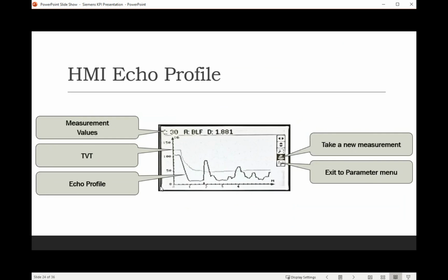Another nice feature with the new HMI version is that you can see the echo profile on the display of the HMI version, whereas with the other standard version, you have to actually use the PDM software on your laptop in order to see the echo profile. But if you go into the menu structure and go to maintenance diagnostics and then hit echo profile, it'll take a snapshot of the process as it sees it. It'll give you your confidence reading, your algorithm, and then also your distance at the top. And then you can also see if there's any obstructions or anything that you need to map out. So a really helpful and easy to use troubleshooting tool with the new HMI version.